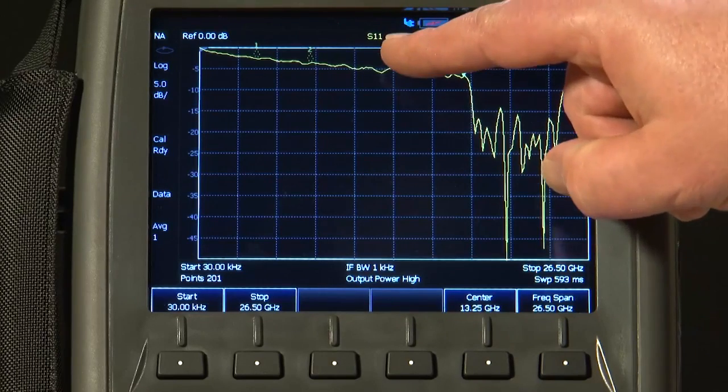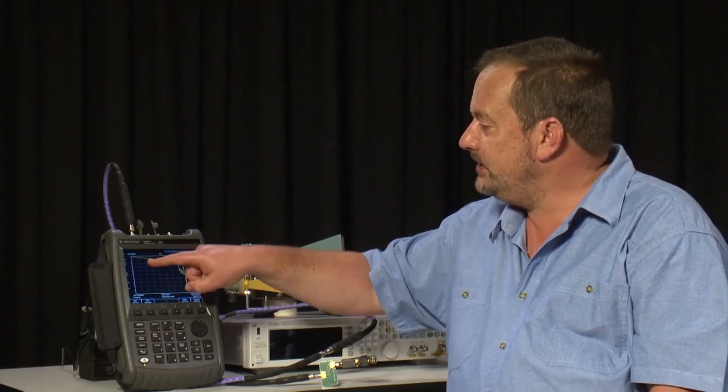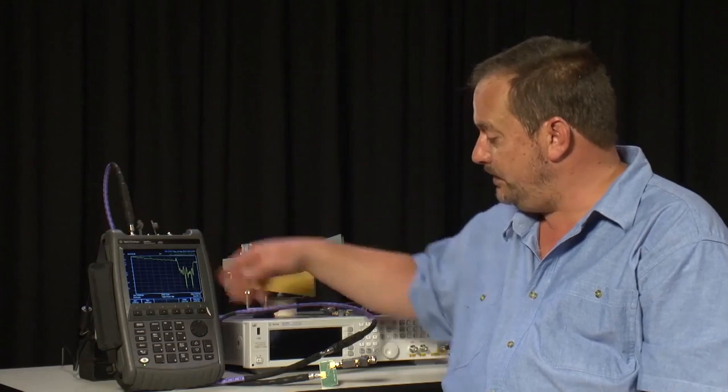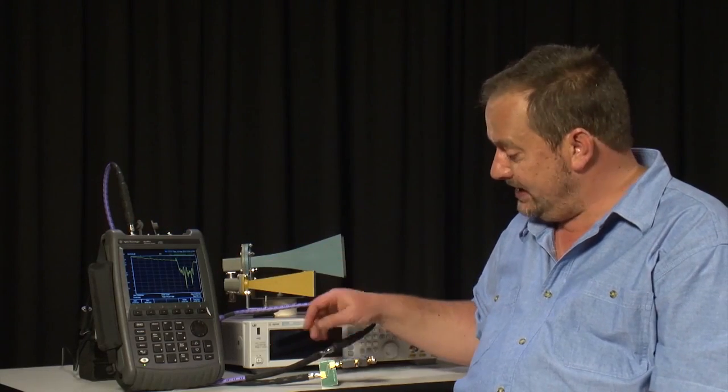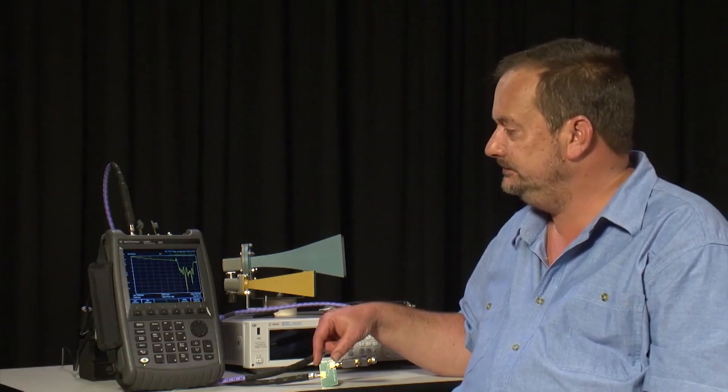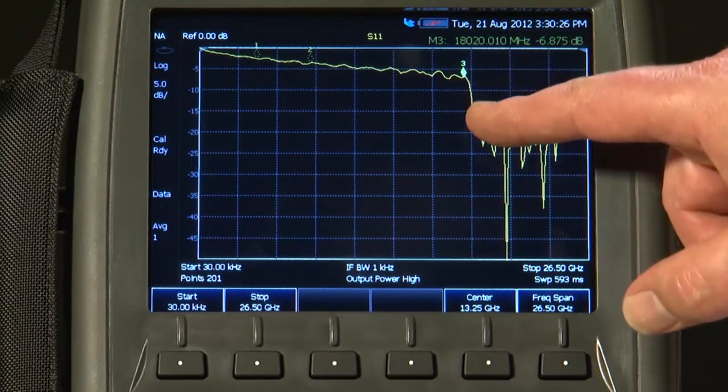You can see here on the display we are measuring S11. That is the return loss of the entire measurement system. So this response here is in fact the return loss of both of my purple cables, the connectors, the launch onto the filter and the filter itself. And the first thing you'll notice is that there is quite a bit of ripple on the return loss trace.